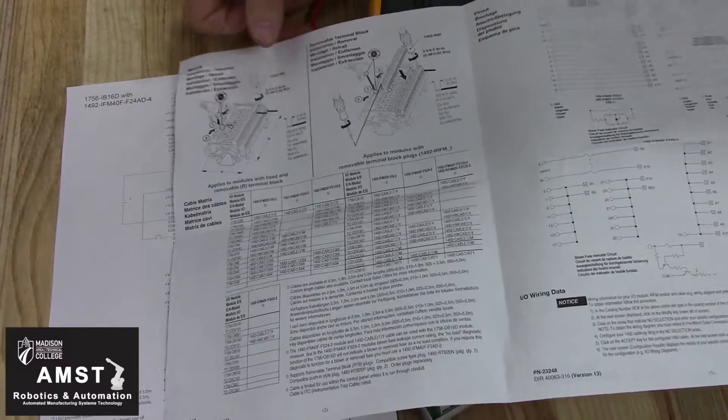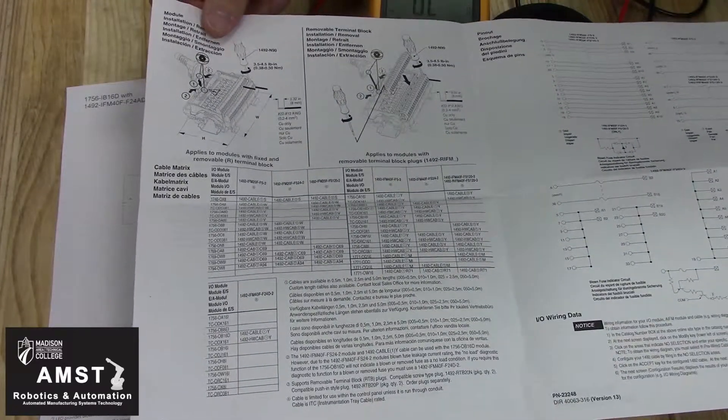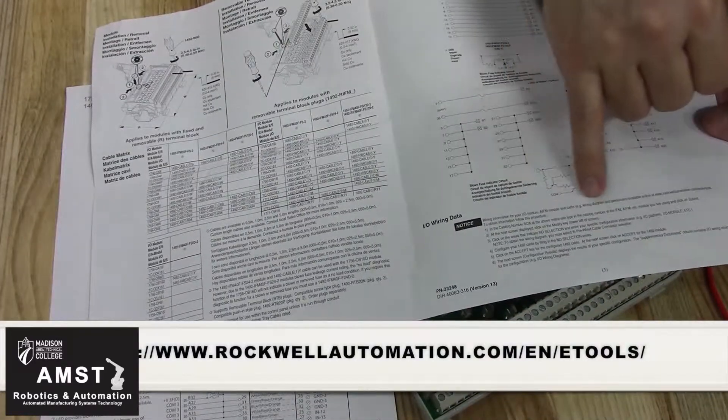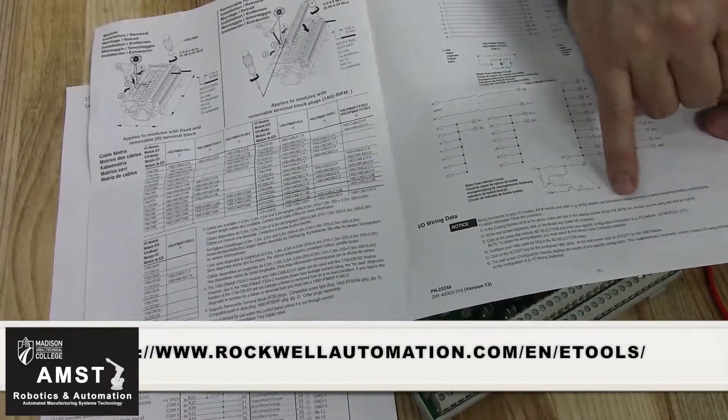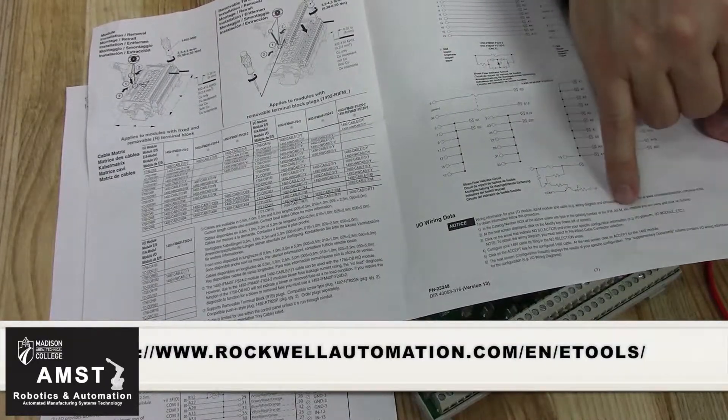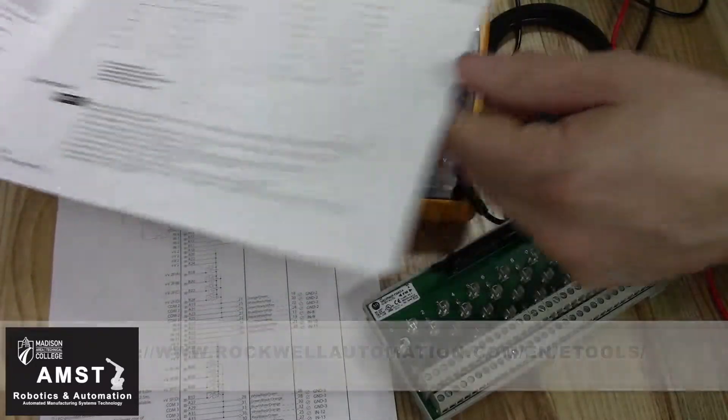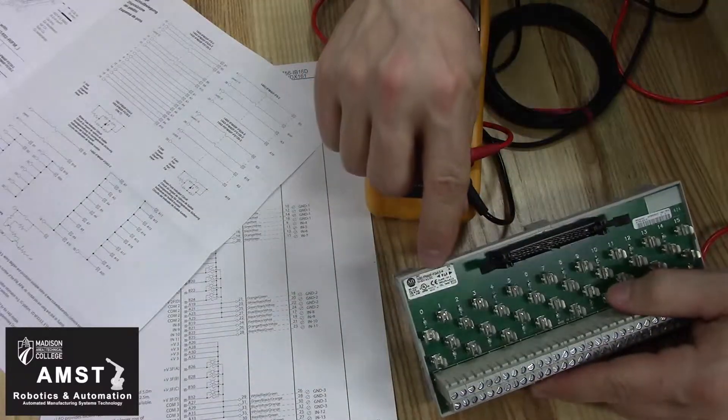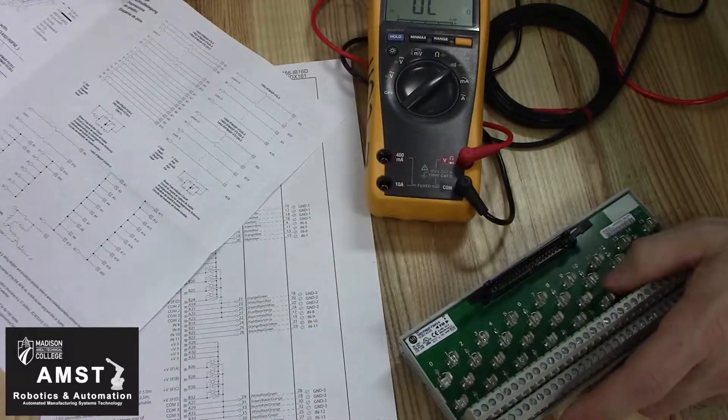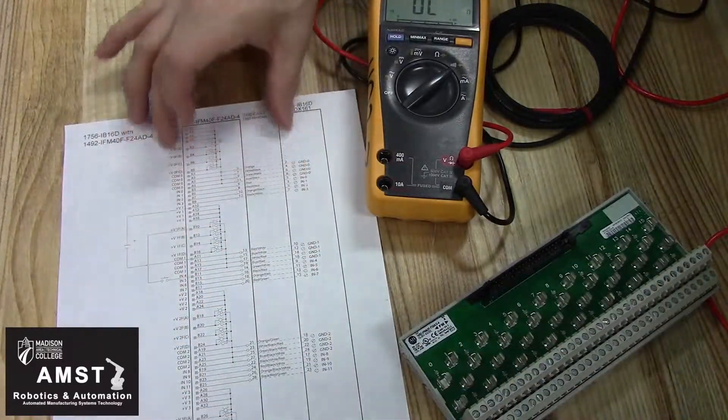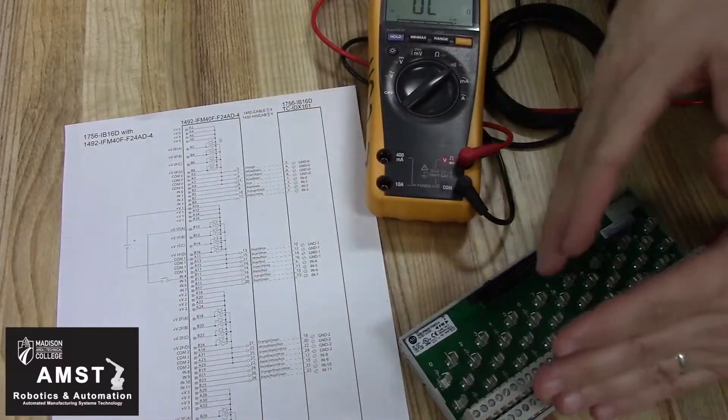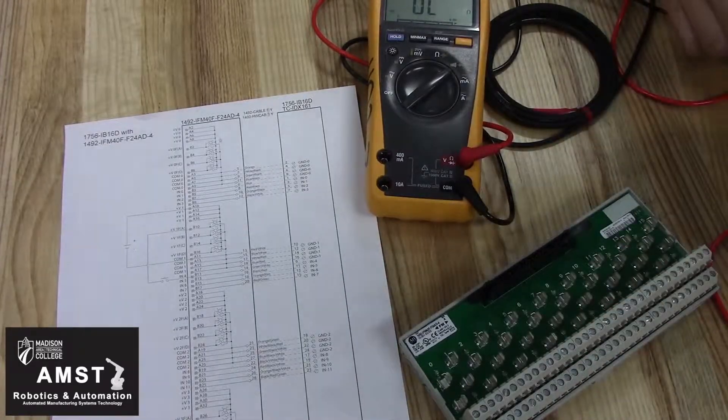Initially, you're going to get this manual that comes with your IFM module, and it really doesn't have enough information. You're going to need to go online to eTools, Allen Bradley's eTools, and put in your very specific IFM catalog number. Once you do that, you'll be able to download a PDF that gives you a very specific pinout for your exact IFM module.